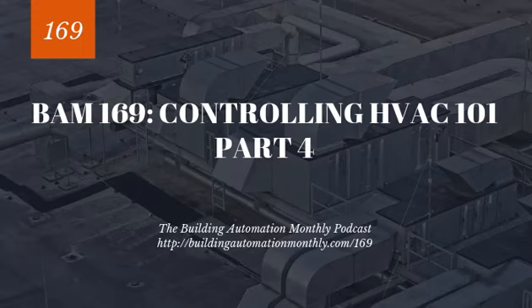Now, there are two forms of lead lag, right? You've got lead lag that is just pure lead lag. Each boiler is sized to handle the building, and you switch over. Or you have lead lag with lag acting as a peak load conditioning device. And you'll see this in chillers too, where lead will handle 80% and then lag will kick in for that last 20%, as well as any demand above your design days.